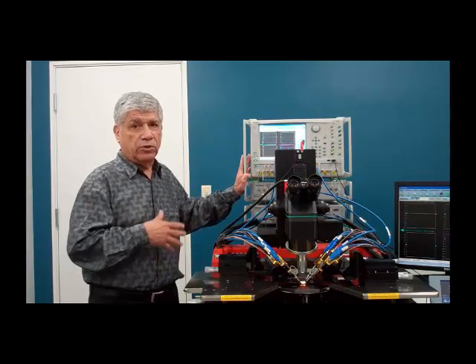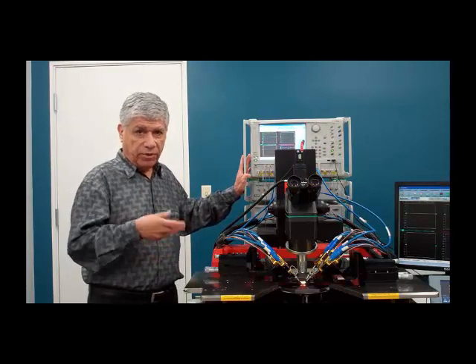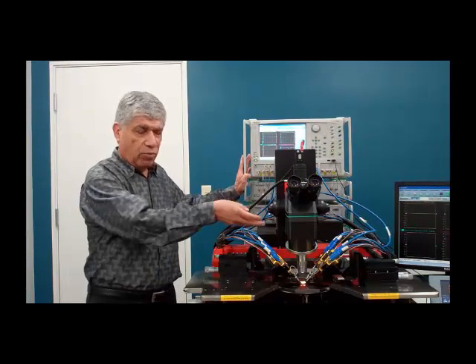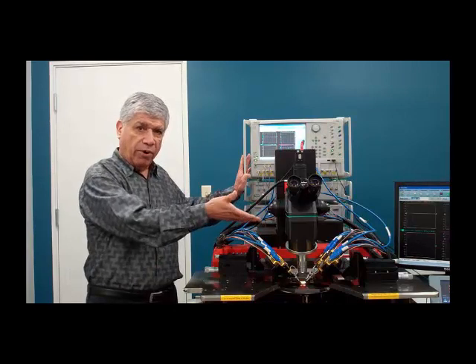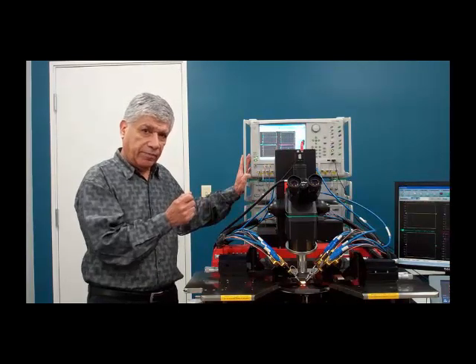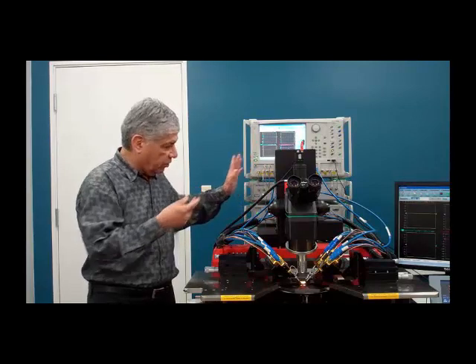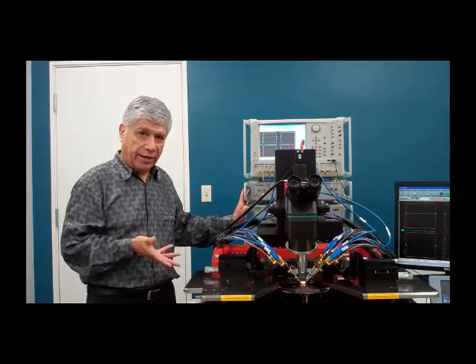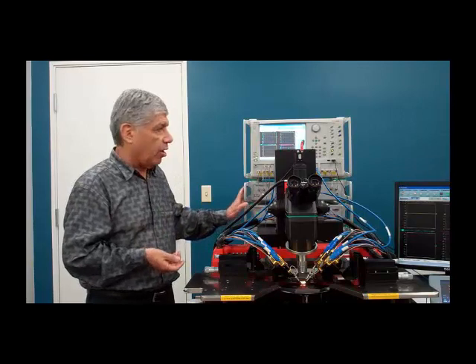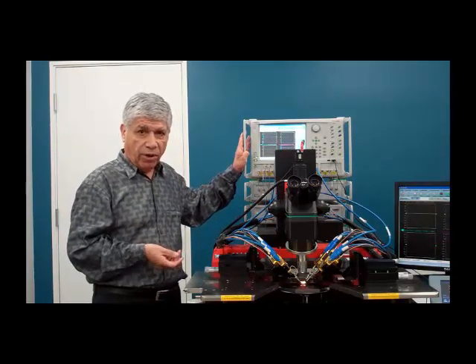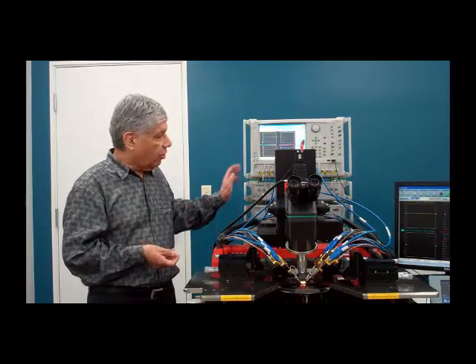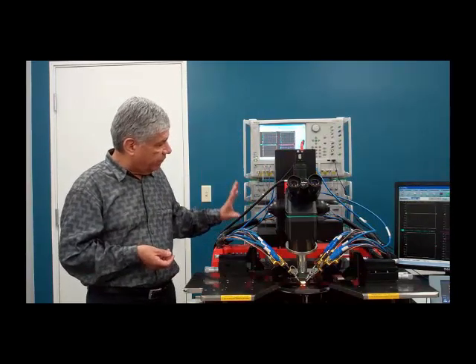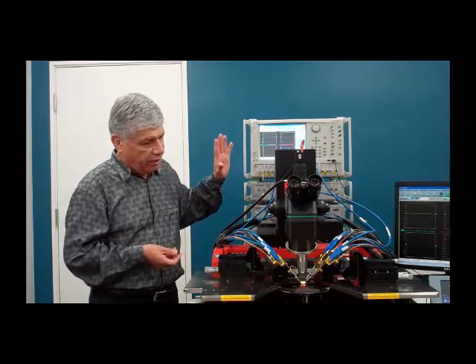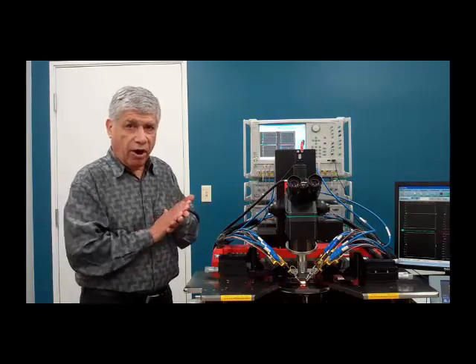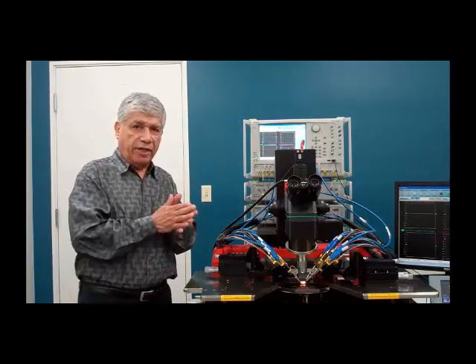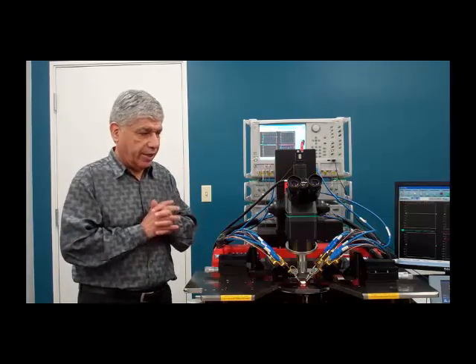Then, if we wanted to increase our port count from 2 to 4, we can add 2 more modules to have 4-port broadband measurement capability. So, of course, if we have 2 more modules, we'll need another test set to do that. Also, in order to increase our baseband ports from 2 to 4, we add a 4-port test set. So in total, we have 4 instruments driving the modules in order to do our 4-port differential measurement, 70 kilohertz to 145 gigahertz in this case.